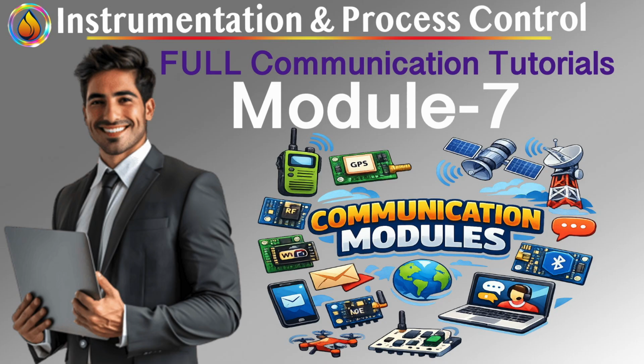Here's the sentence that ties everything together. H1 is a powered distribution system pretending to be a network. Once you see it that way, terminators make sense, spur limits feel obvious, distance rules stop being arbitrary, commissioning becomes methodical. And with that physical discipline understood, you're ready for the final missing piece. If multiple intelligent devices share this powered bus, who controls time and who decides when data moves? That's where link masters, LAS, and deterministic scheduling step in, and where Foundation Fieldbus truly separates itself from everything else.